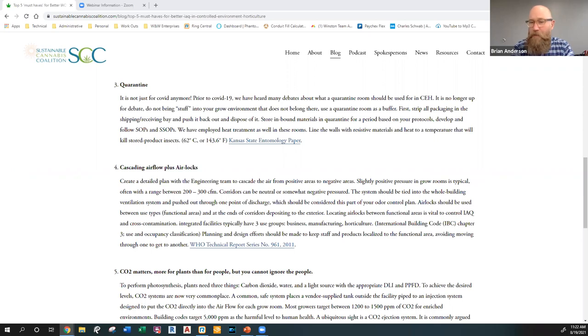So you want to specify that your grow rooms have positive pressure. You get positive pressure by adding cubic feet per minute, CFM. You want 200 to 300, usually 250 CFM of outside air pushed into your grow room so it stays positively pressured. Hopefully, as Anthony said, there isn't some big roll-up door with gaps in it out in the high desert where air is leaking out. You've got a tightly sealed room with no big roll-up doors connecting it to the outside.